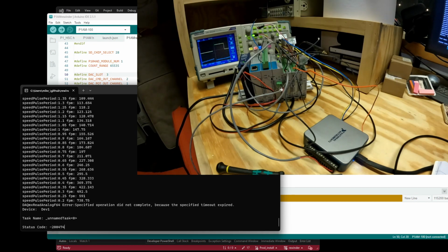And if I jog the plant, you will see on the screen I put in a step response. I'm only going 738 feet per minute, but now you can see this is accounting for transport lag in the system, and that's why we get a fairly relaxed response.